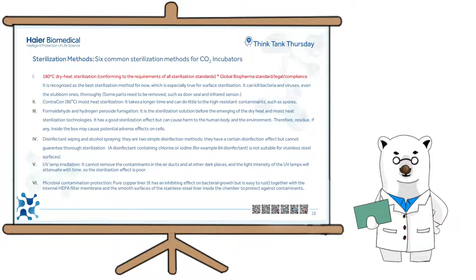Dry heat sterilization at 160 Celsius degrees to 180 Celsius degrees for several hours satisfies several international guidelines for SAL6 sterilization. High temperature dry heat causes cell death through denaturing of all proteins, destruction of nucleic acids, and desiccation. 180 Celsius degrees for 4 hours will kill all known microorganisms, including toughened endospores from bacteria such as anthrax. And this is the very reason why we use 180 Celsius degree dry heat sterilization. Also, in practical use, the sterilization cycles and the recovery are more competitive compared to other producers.